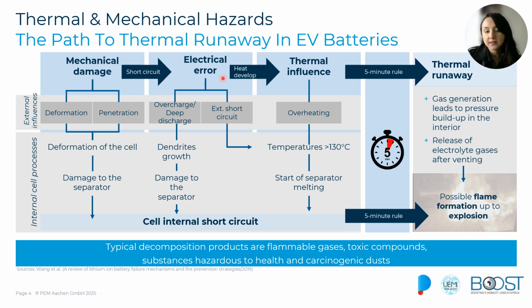We can see that any of the electrical hazards we can have will accelerate the thermal runaway process. One of those electrical hazards is, for instance, external short circuit, as well as internal short circuits caused by mechanical damage. We can also have overcharging or over-discharging, and at the end all of these electrical events will disrupt the normal electrical operation of the battery and generate an excessive amount of heat that will trigger the thermal reaction. Finally, we have the thermal stress that can both trigger this reaction and also be a consequence of all the previous events.